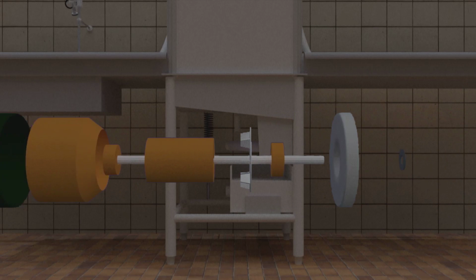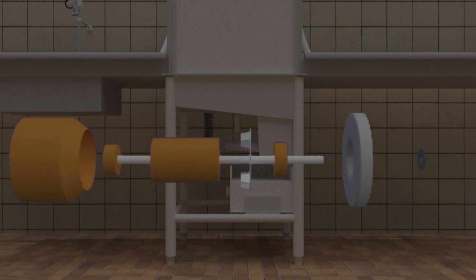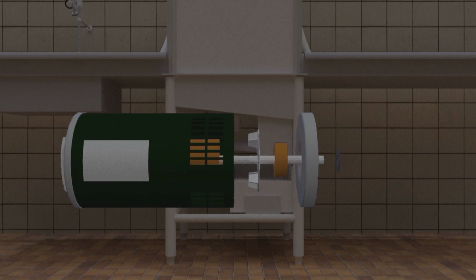In order for the shaft to spin evenly at such a high speed, the motor has 2 or more bearings inside the body which hold the shaft in alignment with the pump. Also spinning with this shaft is an internal fan and a large piece of metal called a rotor. The rotor spins inside an assembly called a stator. Together, these two items convert electricity into movement which spins the shaft. The stator is comprised of a series of copper coils which can often be configured for 2 different voltage inputs, 120 and 230 being the most common.